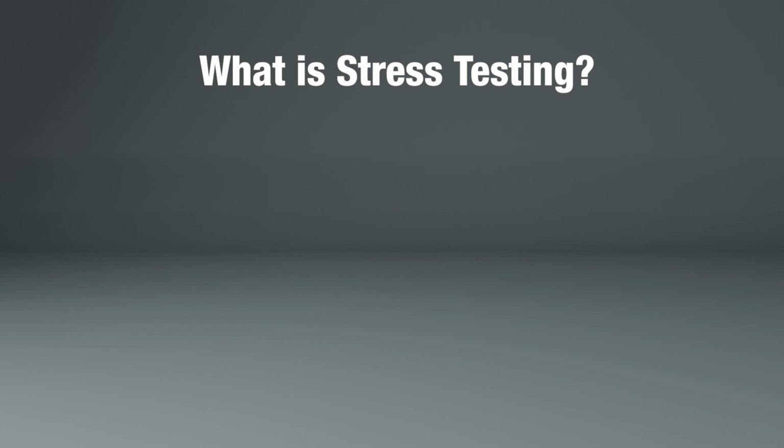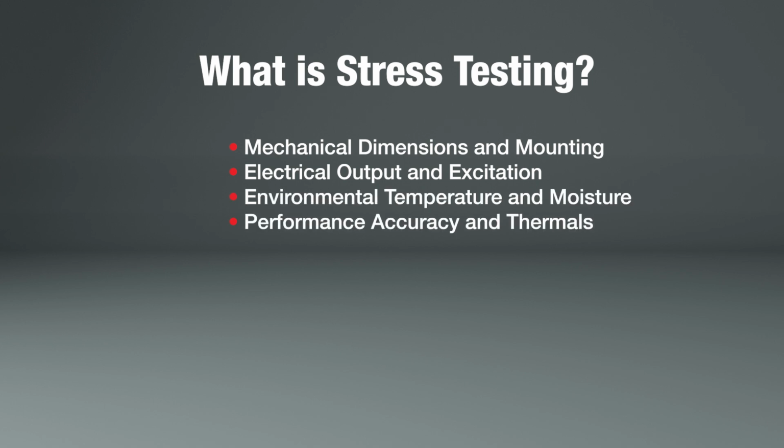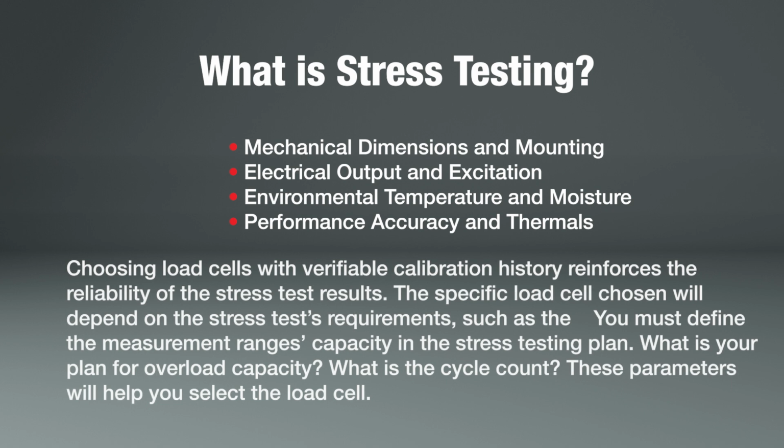Four specifications must be addressed for the stress test application before choosing a load cell: mechanical dimensions and mounting, electrical output and excitation, environmental temperature and moisture, plus performance accuracy and thermals. Choosing load cells with verifiable calibration history reinforces the reliability of the stress test results.